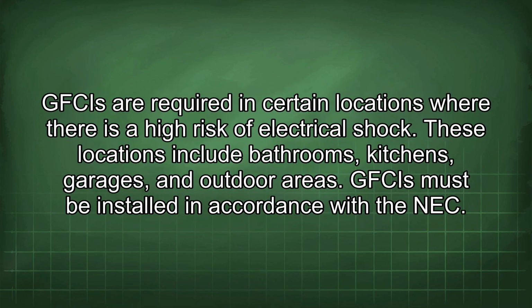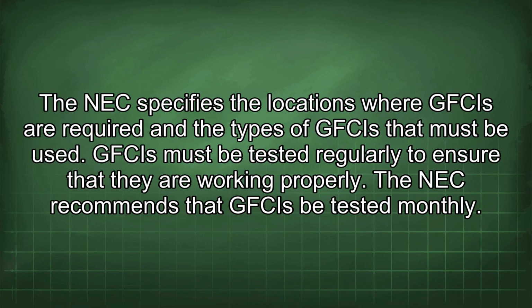GFCIs are required in certain locations where there is a high risk of electrical shock. These locations include bathrooms, kitchens, garages, and outdoor areas. GFCIs must be installed in accordance with the NEC. The NEC specifies the locations where GFCIs are required and the types of GFCIs that must be used. GFCIs must be tested regularly to ensure that they are working properly. The NEC recommends that GFCIs be tested monthly.